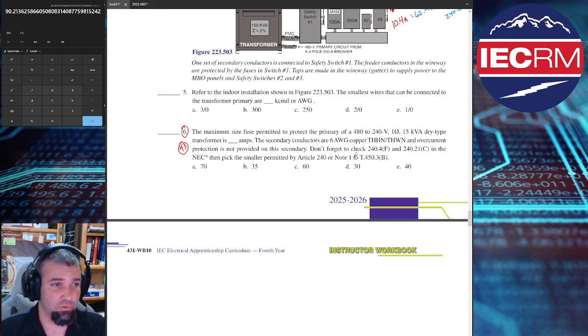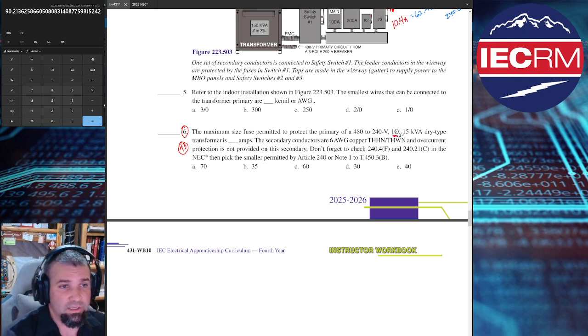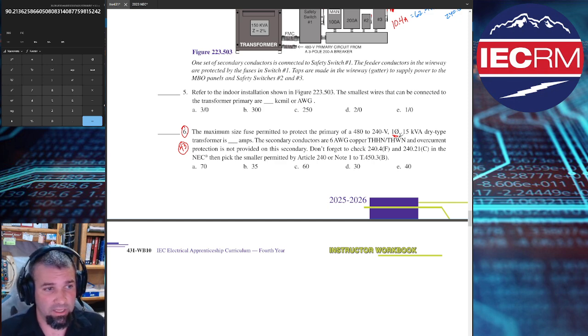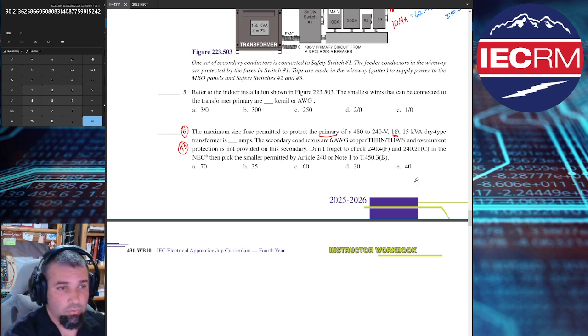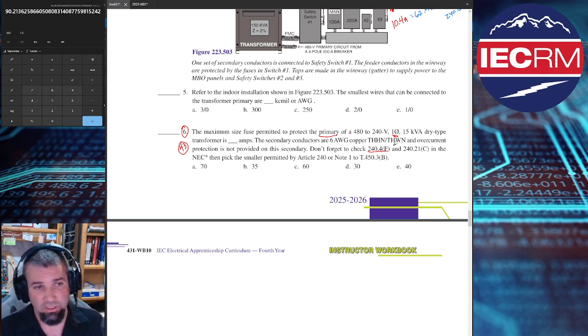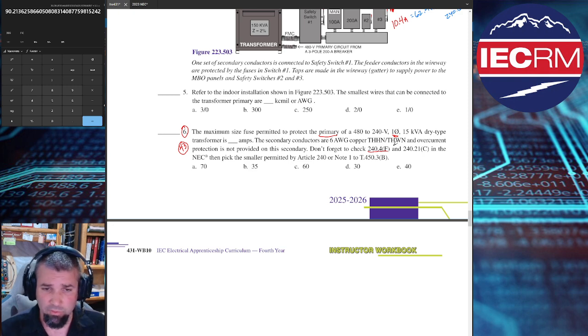This says the maximum size fuse permitted to protect the primary of a 480 volt to 240 volt single phase, we are in single phase, 15 kVA dry type transformer is how many amps? Okay, we're talking about primary protection. The secondary conductors are 6 gauge copper THHN, THWN, and overcurrent protection is not provided on the secondary. Don't forget to check 240.4F, which we will do, and 240.21C in the NEC. Then pick the smaller permitted by Article 240 or Note 1 of 450.3B. Okay, so we have to do both of these calculations, and then we are going to do a comparative analysis, and we are going to pick the appropriate one for our circumstance.